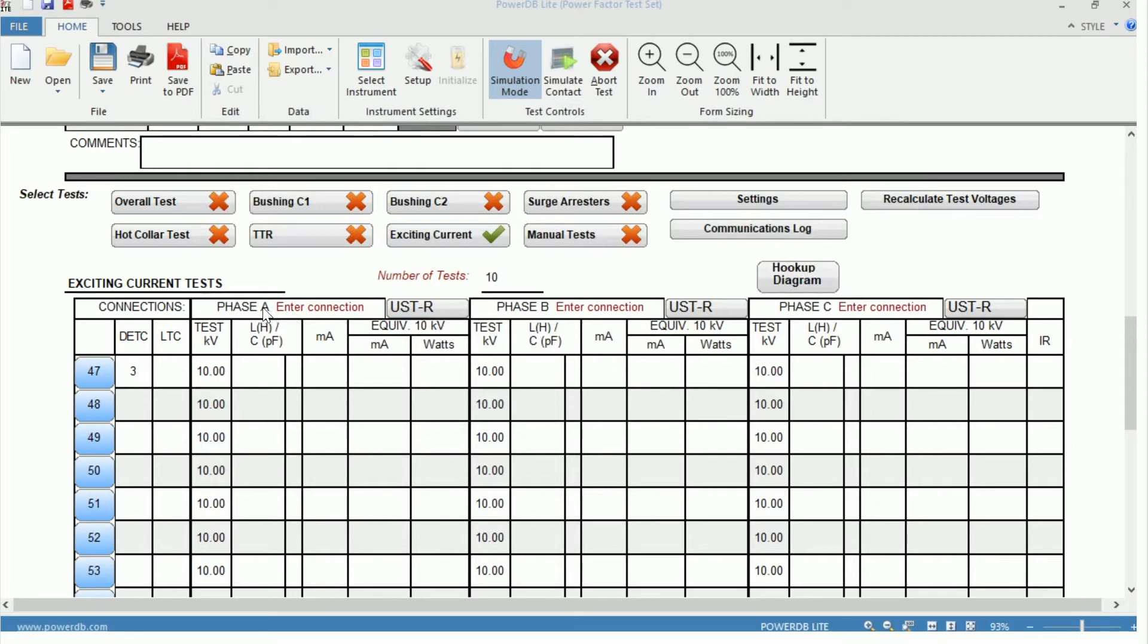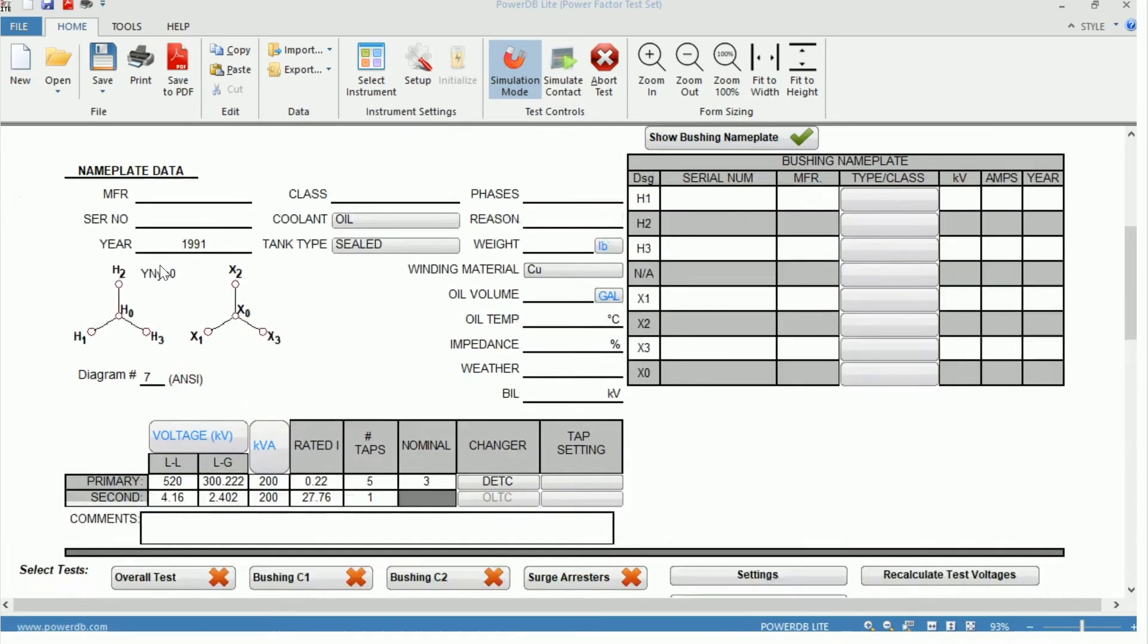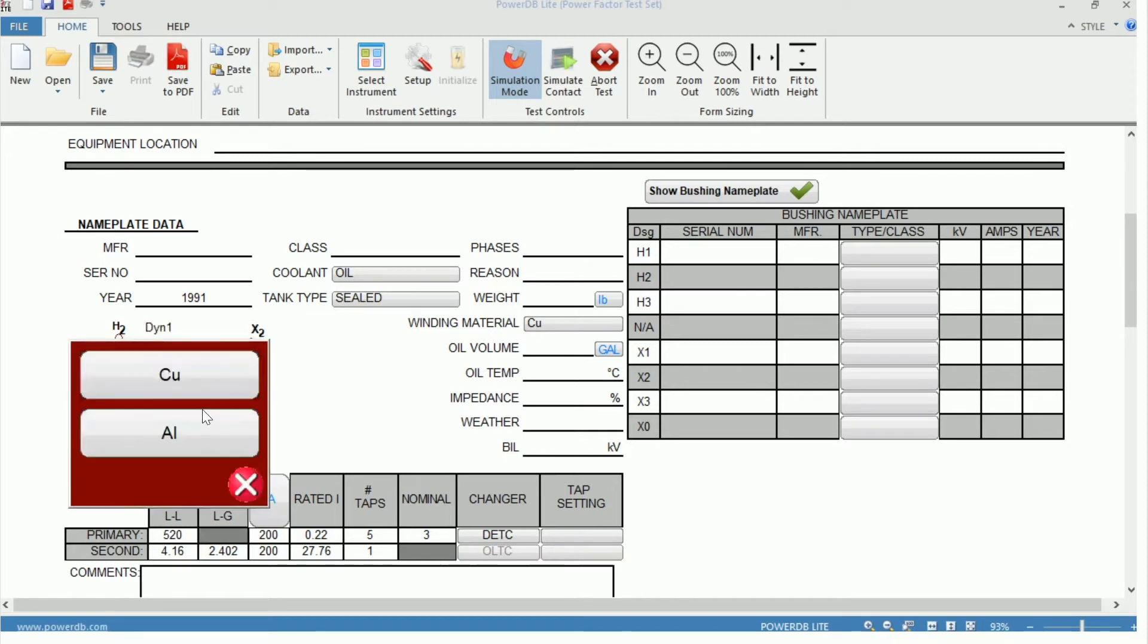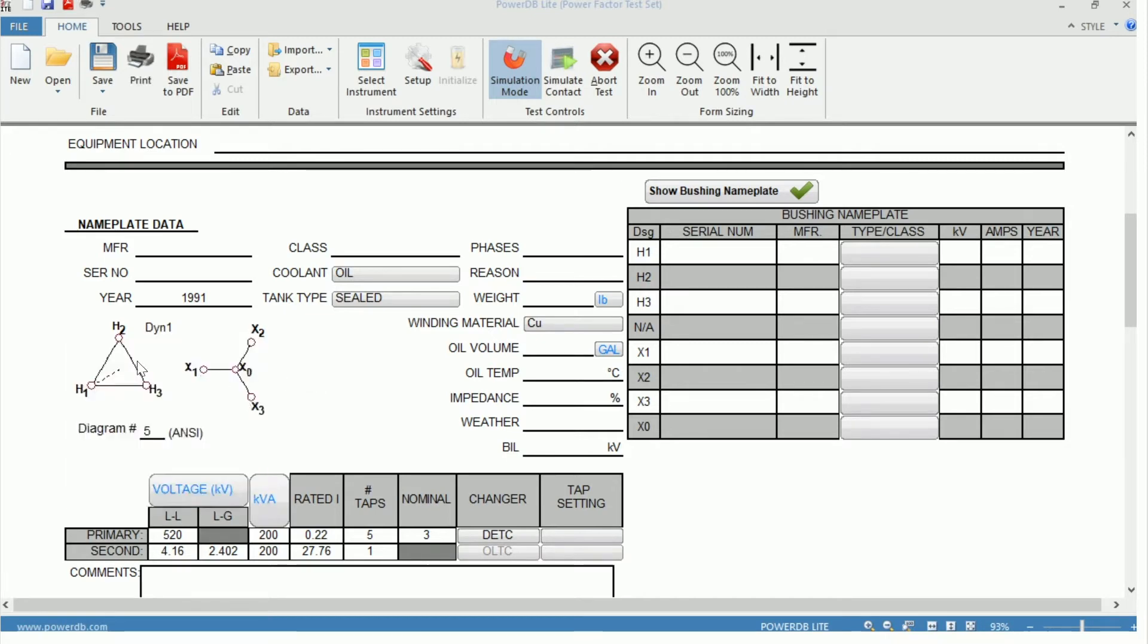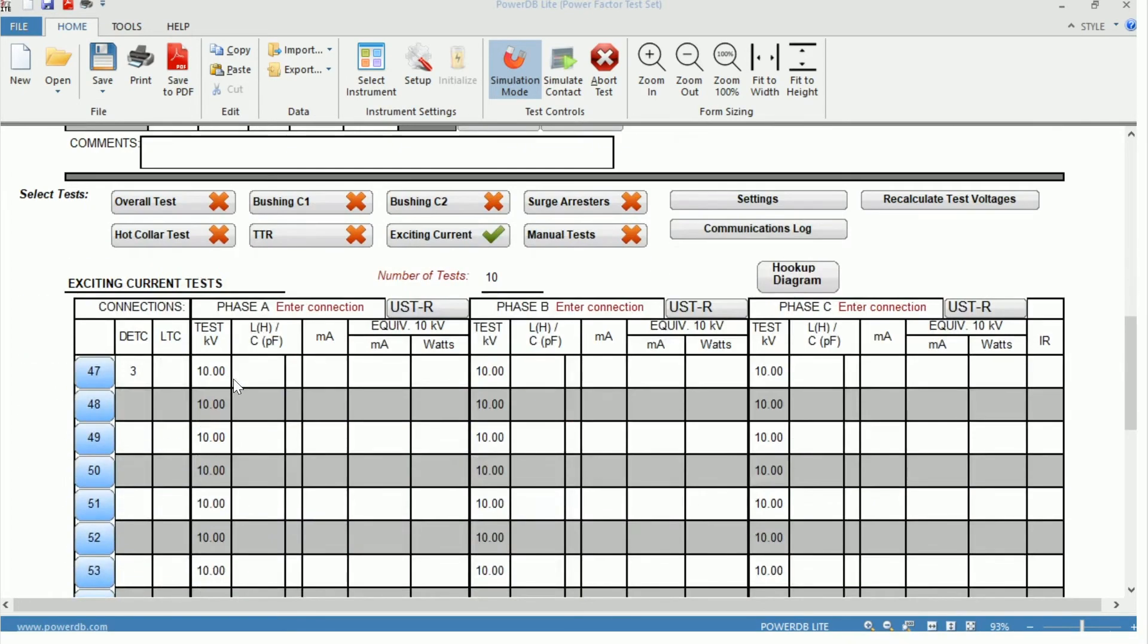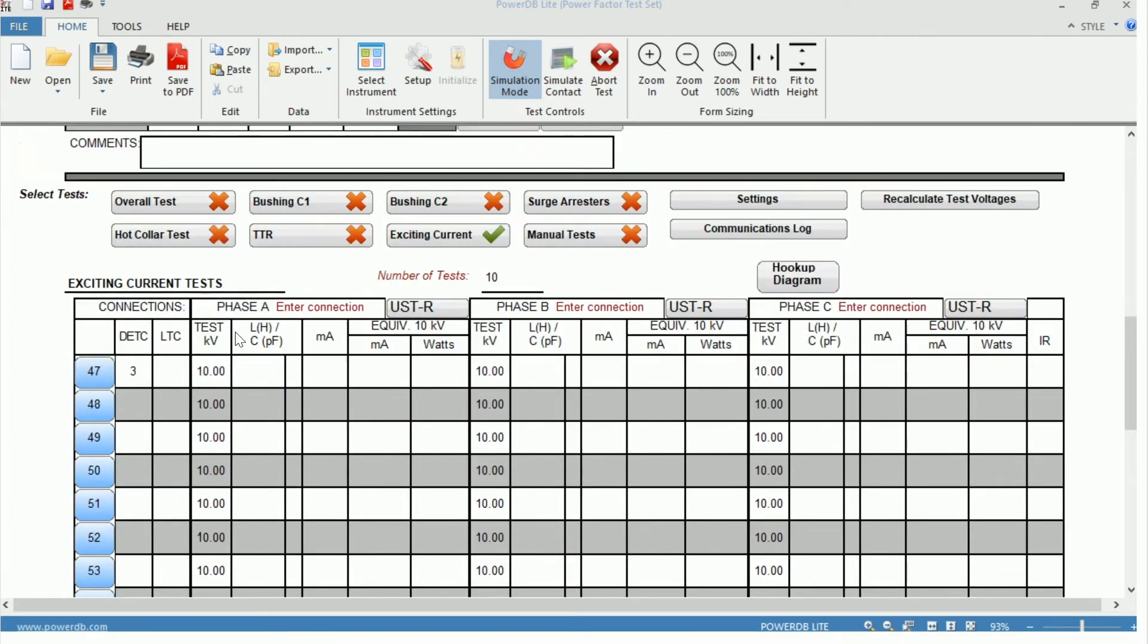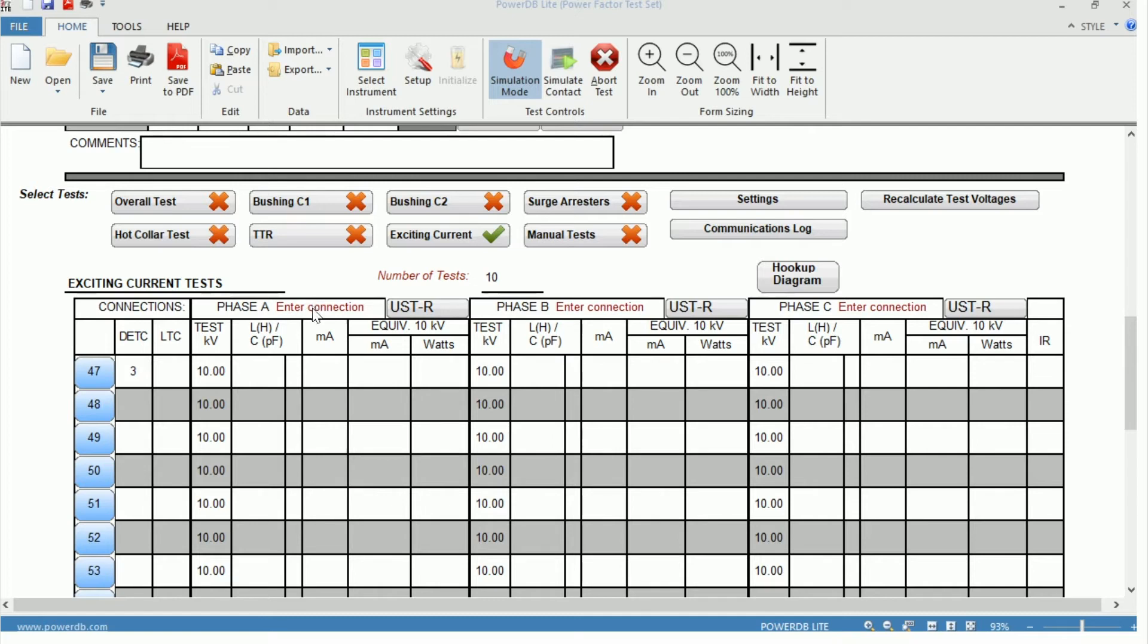Looking also, we can change over to a more common configuration, so a DYN1. We have our delta and our YN1. And we can see here at the top, phase A, B, and C. And next to those are enter connections. What that is, just similar to the connections on your tap changer, this allows you to enter the connections made on the bushings themselves. The first bushing entered would be where the high voltage is applied, and the second bushing entered would be where the measured lead is applied. In this case, the red lead.